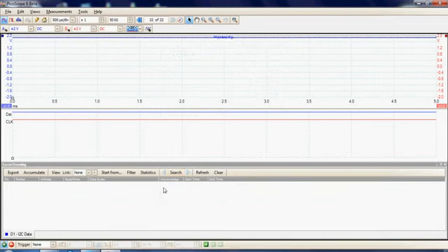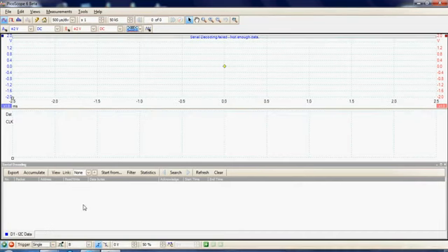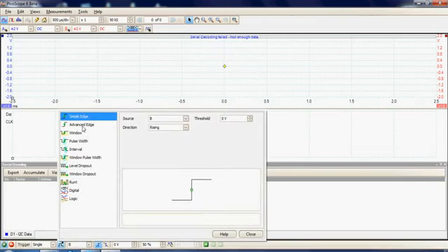So now we have a third window opened where the decoded data will appear when the instrument triggers and acquires data. So the final thing to set up is the trigger. Trigger condition at present is none. Typically these acquisitions would probably be a single shot when you acquire a burst of data, and the actual trigger conditions are under the icons here. These are the analog conditions: edge triggers, advanced and windows, and pulse width triggers, and these are the two new icons for the digital data.